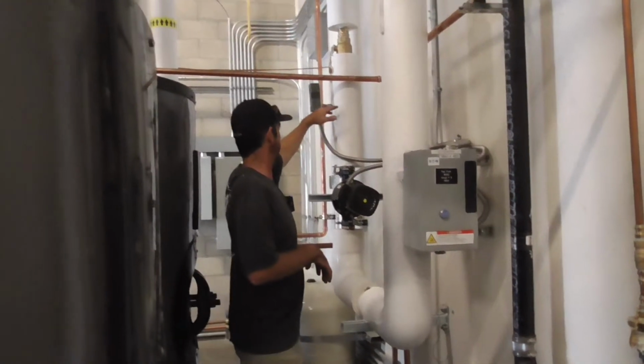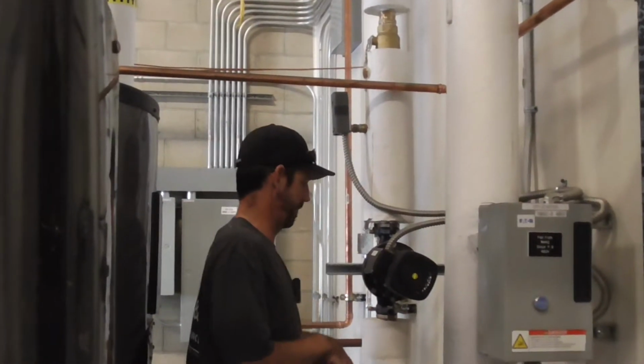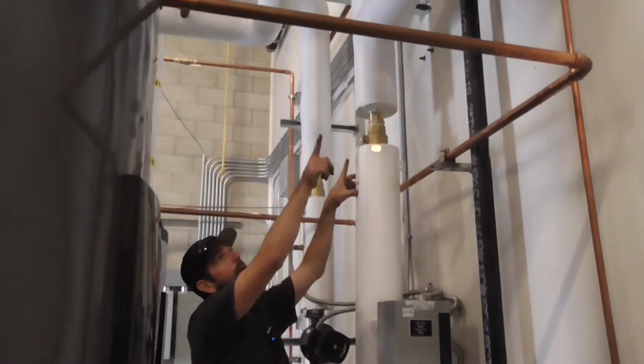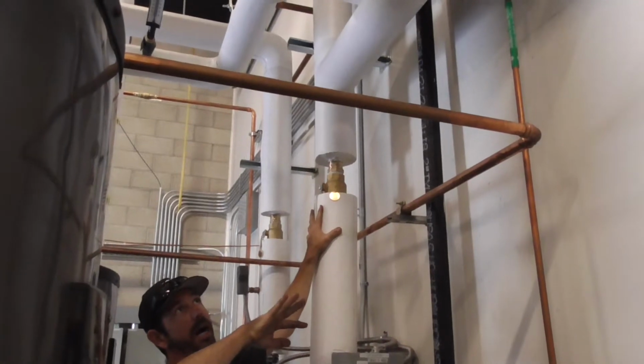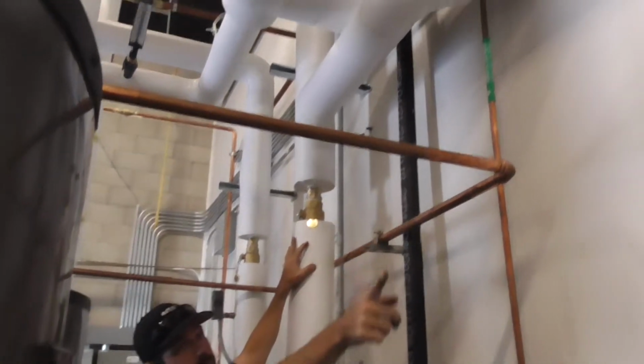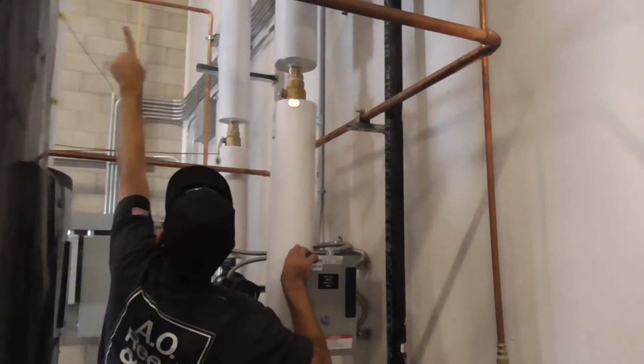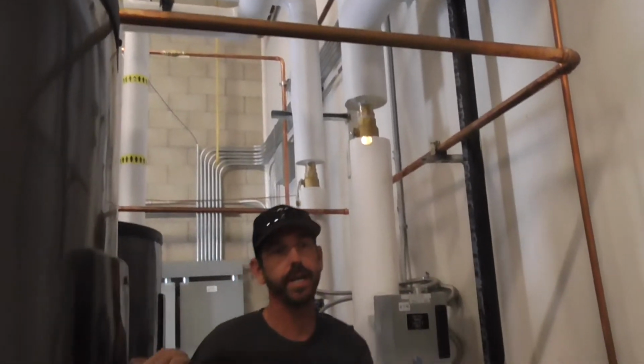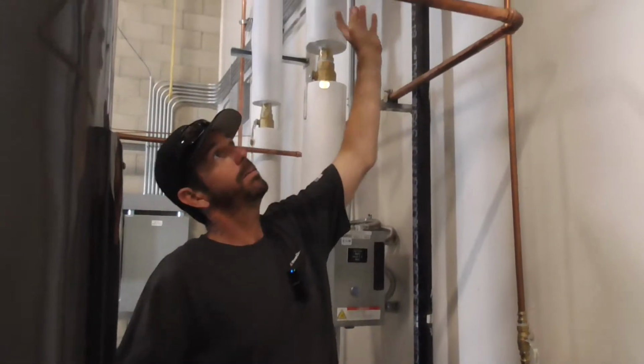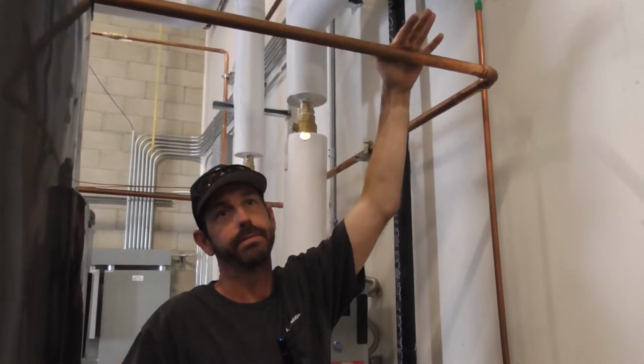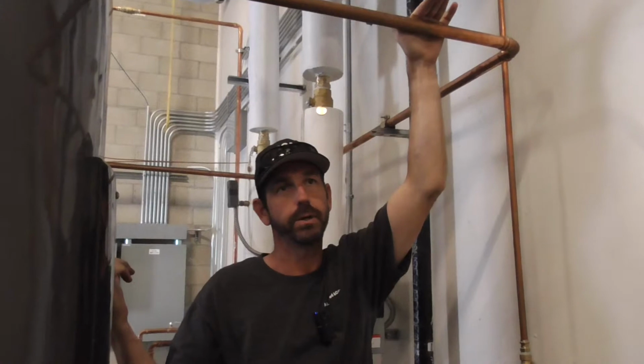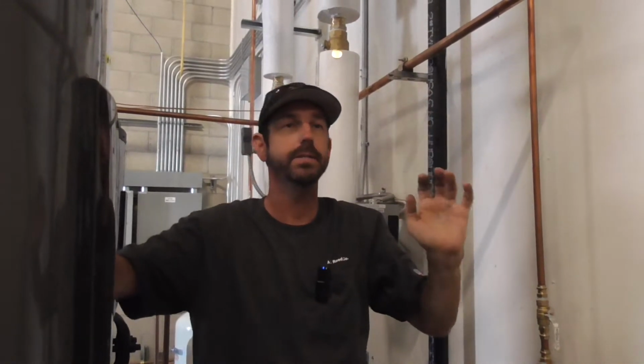And that gets drawn back through here. So this is our return from the building, comes back, okay? And we're pumping up. Now this is where we're balanced. We have a line that goes back to the cold of the mixing valve, okay? We have another line that keeps going back up, back into the cold makeup to the storage tanks. So roughly, when we have this return with the mixing valve, about 80% of the water comes back through your mixing valve, okay? And about 20% goes to your heating source. Then it gets fine-tuned from there, okay? We want to always maintain 120, like the 118 leaving the mixing valve. And again, this is under no use.